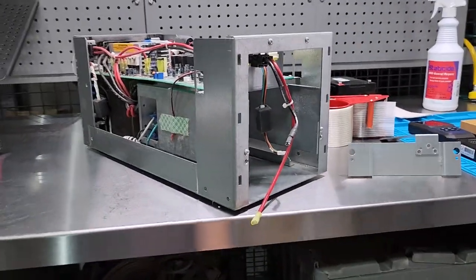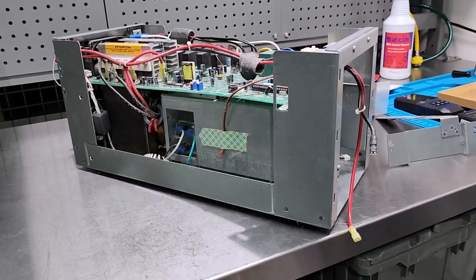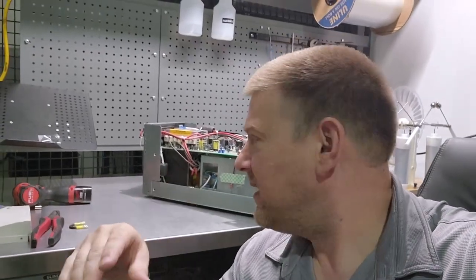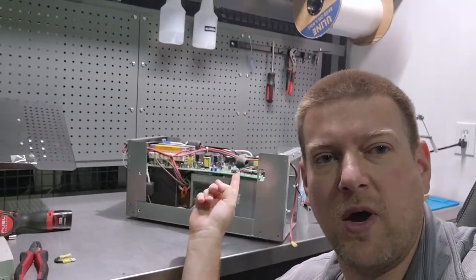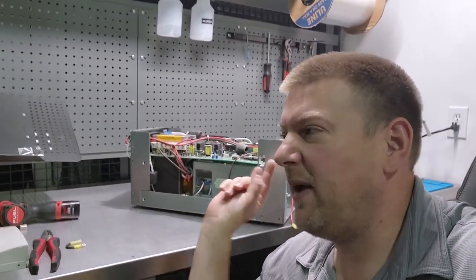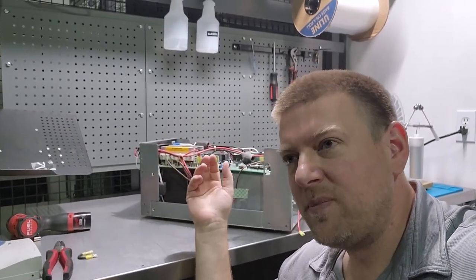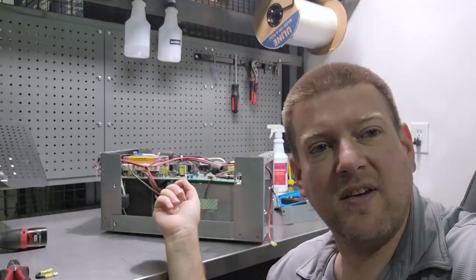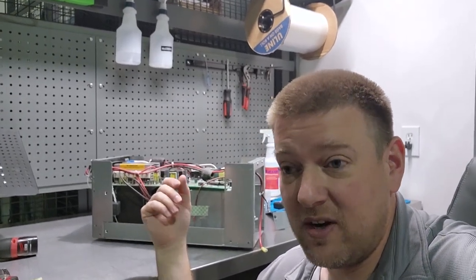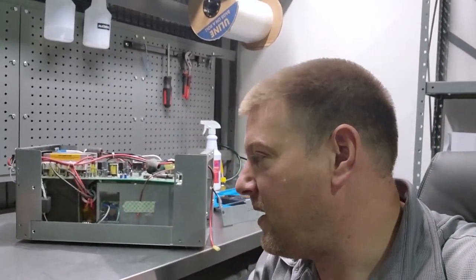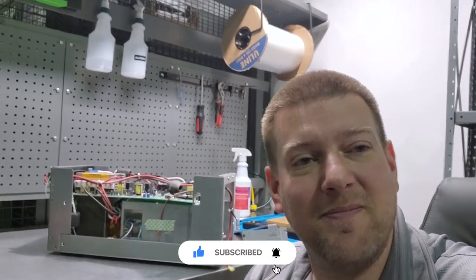That is the inside of a heavy duty, very nice commercial size 1200 VA UPS system. It's just a brief overview. As much as I can do because I don't have a camera person and I don't have a tripod. Really not that complex. Just make sure you do a good inspection of all your terminals and your electrolytic capacitors. Because if this guy is in a large heated environment and under a lot of load, it puts a lot of wear and tear on the electrolytics. They do leak. And when they short internally, it creates all sorts of other problems. It can even pop some of these fuses that you see up here on the main board, usually near the battery incoming terminals. That's UPS system in a nutshell. If you guys like it, let me know. Give me a thumbs up. And please, guys, subscribe.